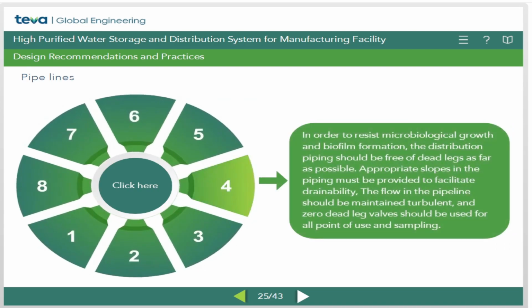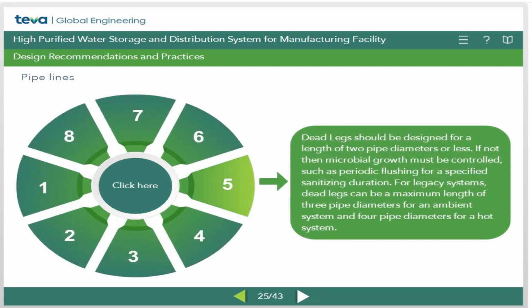In order to resist microbiological growth and biofilm formation, the distribution piping should be free of dead legs as far as possible. Appropriate slopes in the piping must be provided to facilitate drainability. The flow in the pipeline should be maintained turbulent, and zero dead leg valves should be used for all point of use and sampling. Dead legs should be designed for a length of 2 pipe diameters or less. If not, then microbial growth must be controlled, such as periodic flushing for a specified sanitizing duration. For legacy systems, dead legs can be a maximum length of 3 pipe diameters for an ambient system and 4 pipe diameters for a hot system.